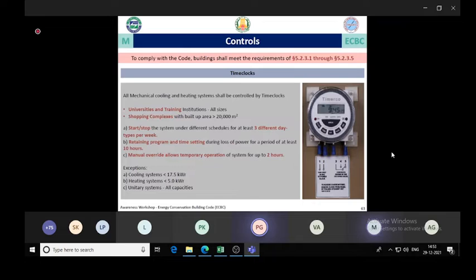So next mandatory one is the time clocks. So this is applicable for any commercial building more than 20,000 square meter, and also universities, education institutions of all sizes. So these buildings should have an automatic timer control system which can operate the HVAC systems based on, for example, morning 8 o'clock should be switched on and evening 6 o'clock should be switched off. So those kind of control should be incorporated in the HVAC. This is mandatory.